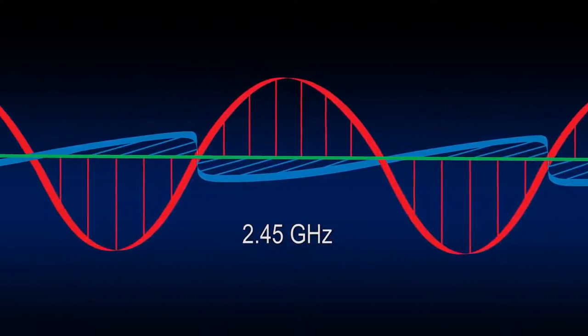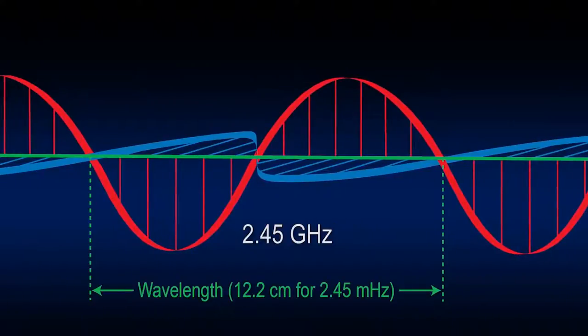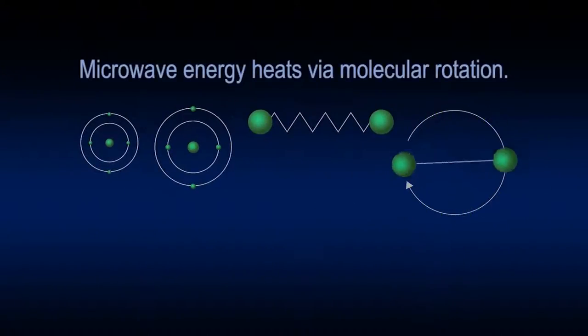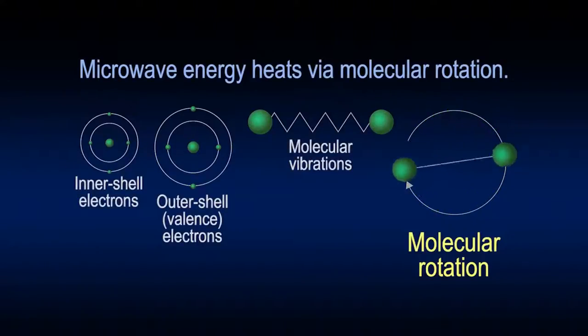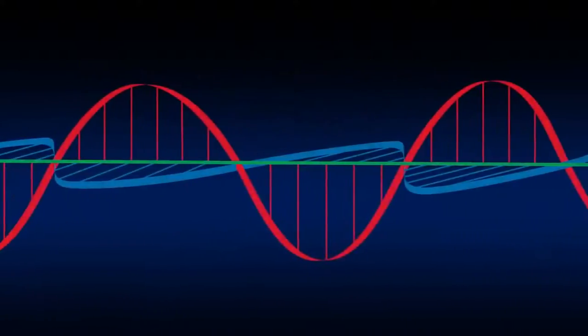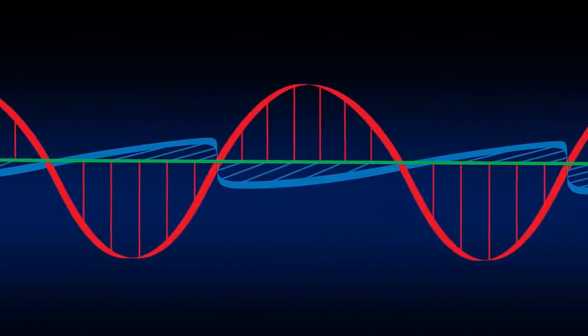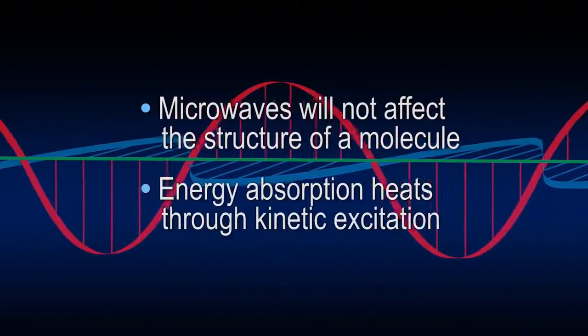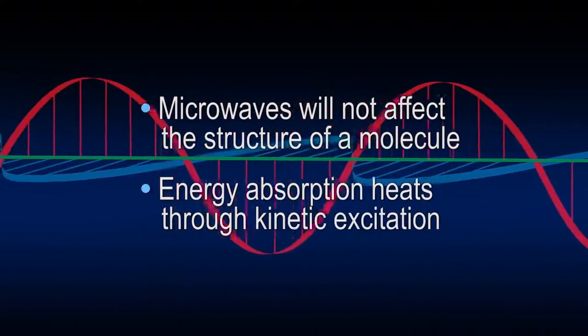CEM instruments use microwave energy with a frequency of 2.45 gigahertz. This frequency most efficiently heats general laboratory scale samples. A common early misconception about microwave energy is that it can make or break chemical bonds. But microwave photons are low energy sources and are comparatively very low in energy relative to the energy required for molecular bonding. Microwaves only induce molecular rotation and do not affect the structure of a molecule. Energy absorption heats purely through kinetic excitation.